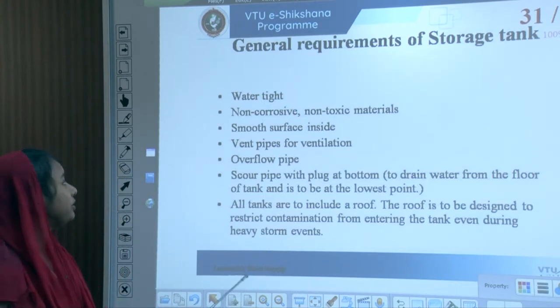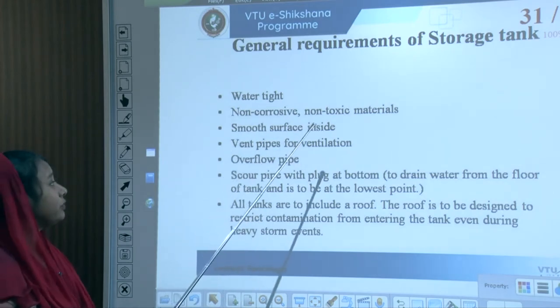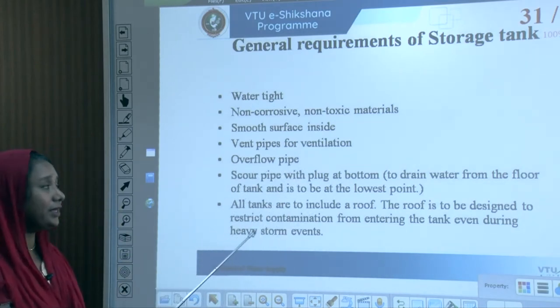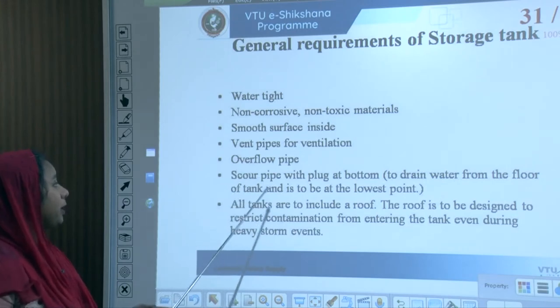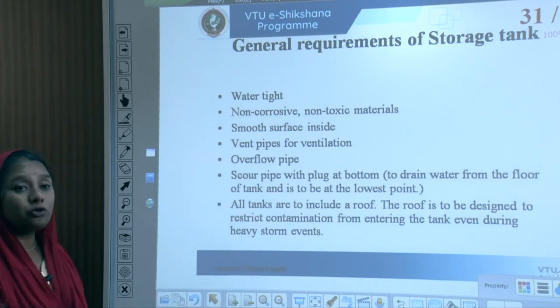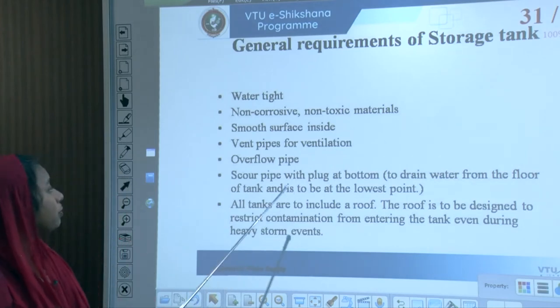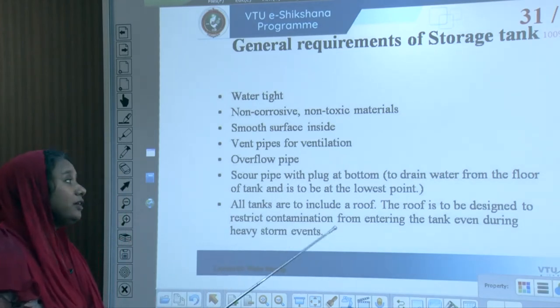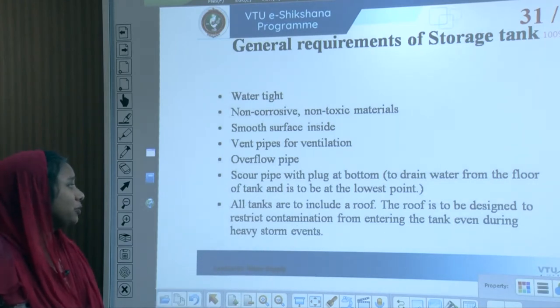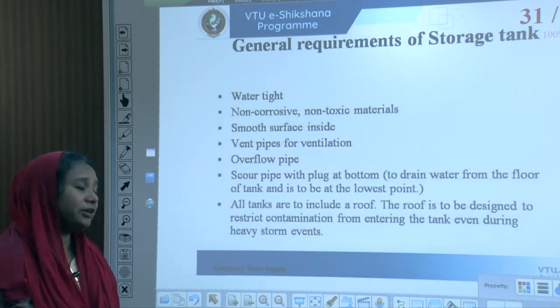General requirements of a storage tank: it should be watertight, non-corrosive, non-toxic, with a smooth interior surface. It should have vent pipes for ventilation, an overflow pipe, and a scour pipe with a plug at the bottom to drain all water — located at the lowest point for cleaning the tank. All tanks must include a roof, designed to prevent contamination even during heavy storms.